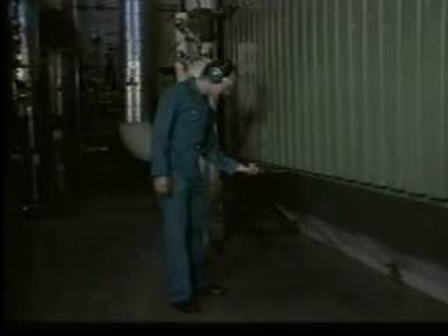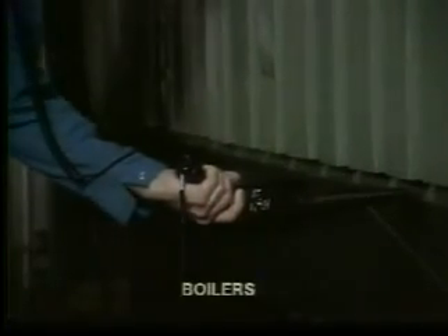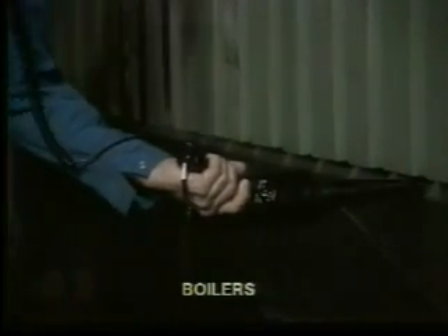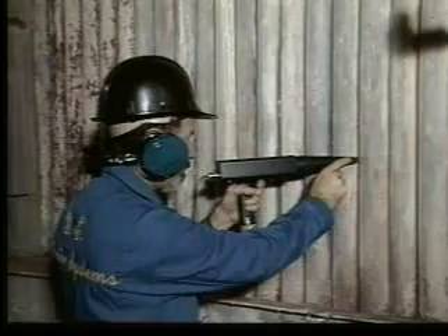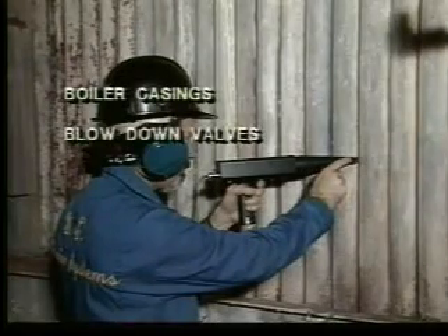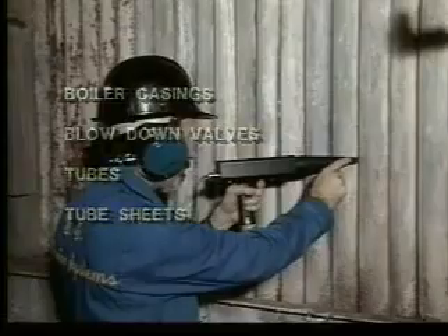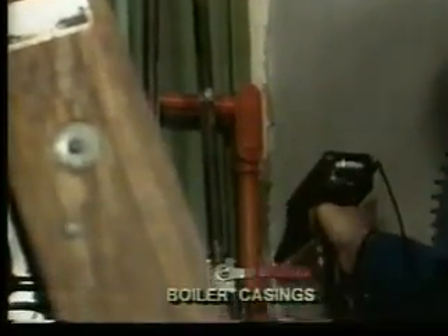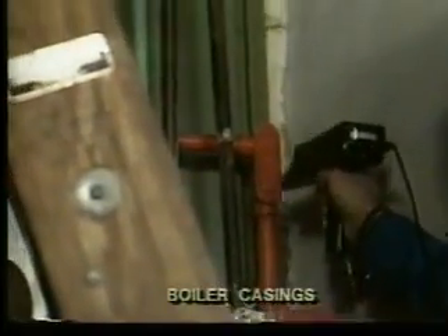Next, we'll take a look at tests for boilers and condensers. This program is concerned with boilers which have tubes or tube sheets which can be accessed for pressurizing and scanning. We will discuss testing boiler casings, blowdown valves, tubes, and tube sheets. Boiler casings are tested using the ultraprobe scanning module in the fixed band. Scan the casing itself at a set distance. Listen.